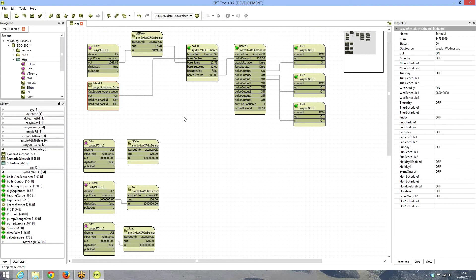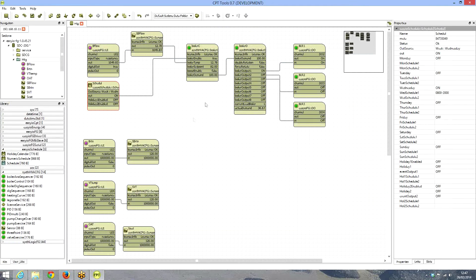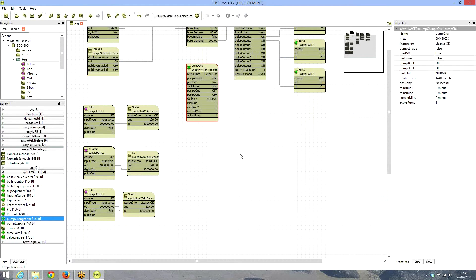The next thing is to control the twin primary pumps. We have twin primary pumps and, let's assume, a flow switch. When we send the signal to ask the pumps to run, if we don't detect flow after a while, we rotate the pump. So we have flow failure monitoring in the system.